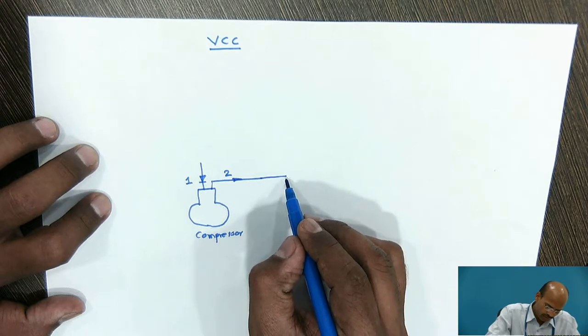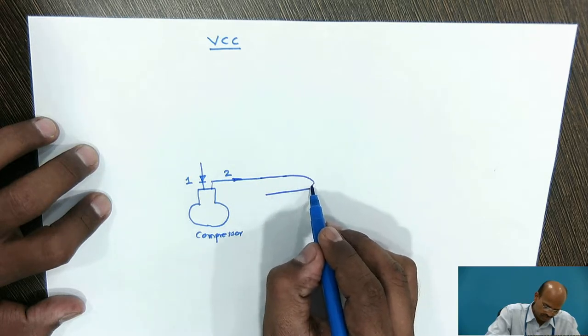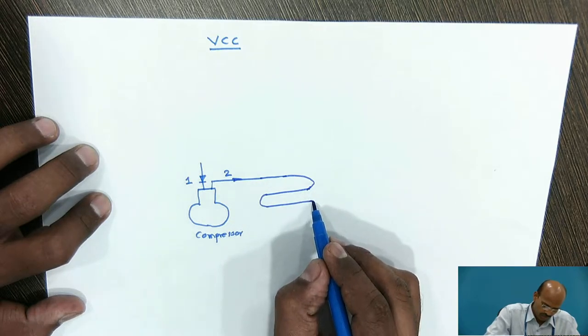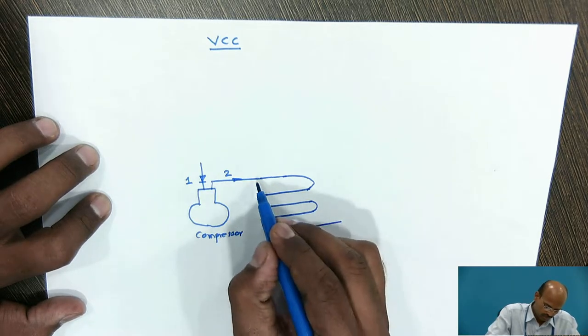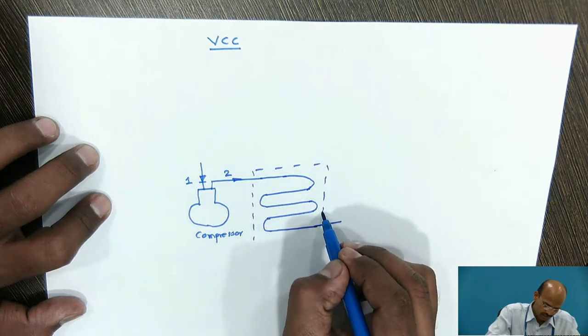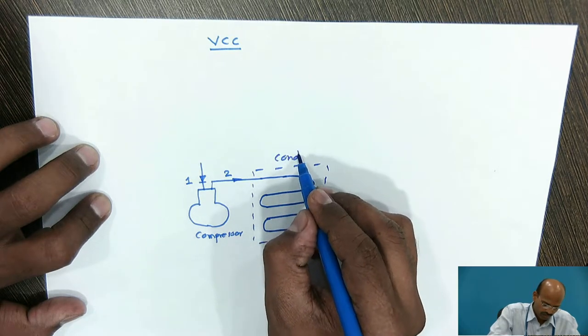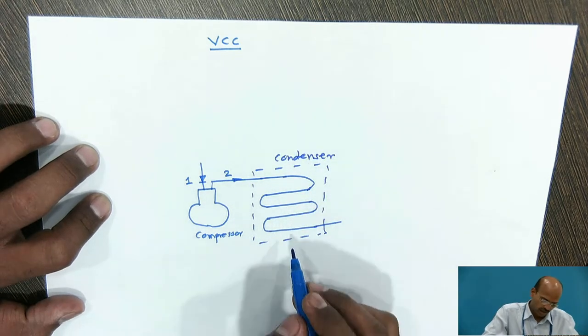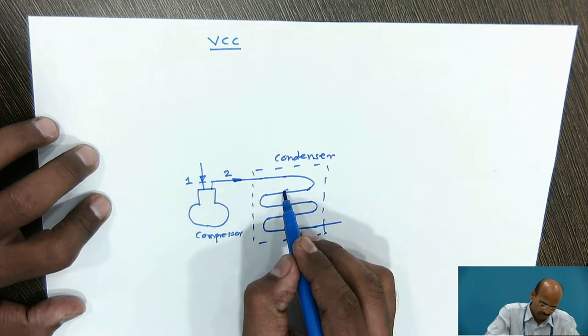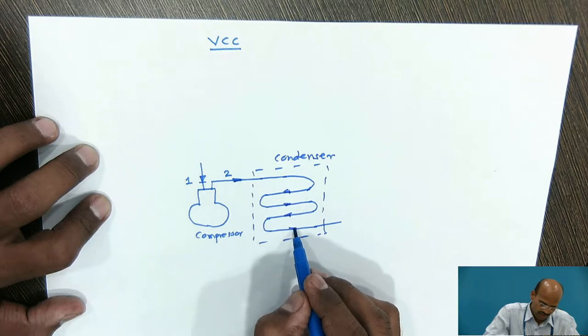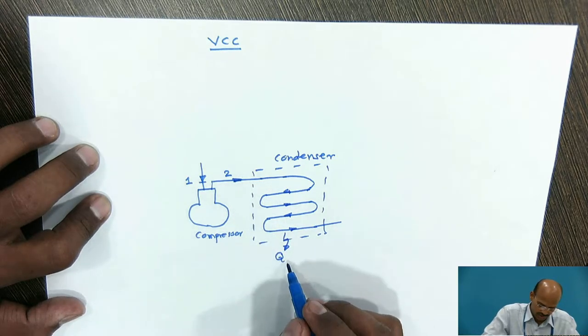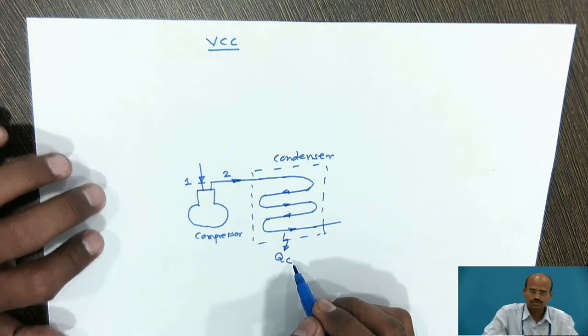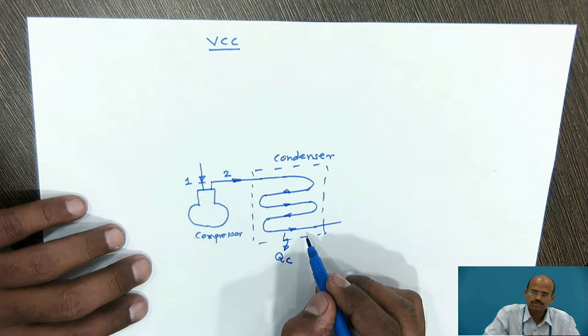This superheated steam is passed through the condenser. The condenser may be tube-in-tube type, shell-and-tube type, or shell-in-coil type. The second device is the condenser. As the superheated vapor flows through the condenser tubes, there will be heat rejection to the surrounding. The total amount of heat rejected by the superheated refrigerant is denoted by QC. The condensation process is an isobaric process — meaning constant pressure heat rejection.